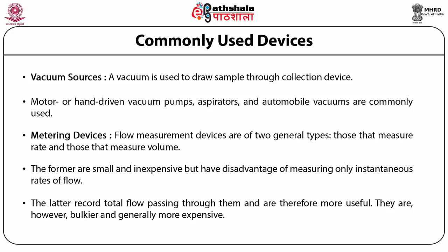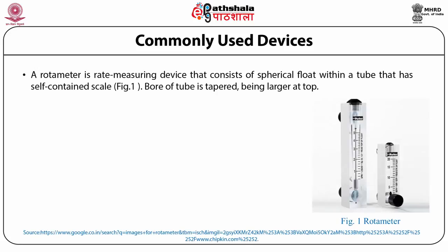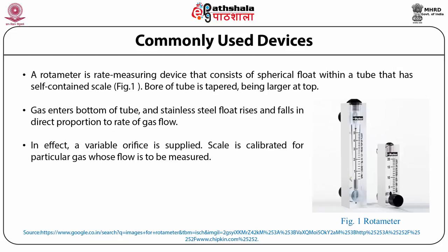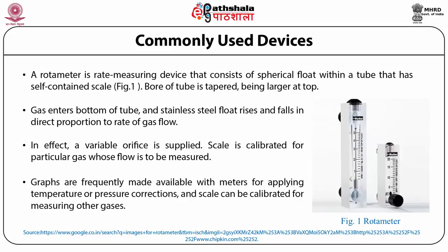A rotameter is a rate-measuring device that consists of a spherical float within a tapered tube, larger at the top. Gas enters the bottom of the tube and a stainless steel float rises and falls in direct proportion to the rate of gas flow, effectively supplying a variable orifice. The scale is calibrated for a particular gas, for example air, whose flow is to be measured. Graphs are frequently made available with the meters for applying temperature or pressure corrections, and the scale can be calibrated for measuring other gases.